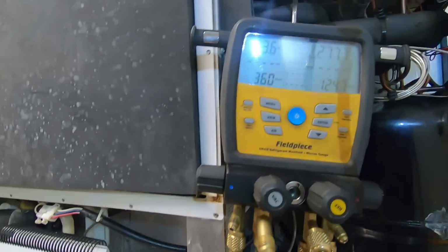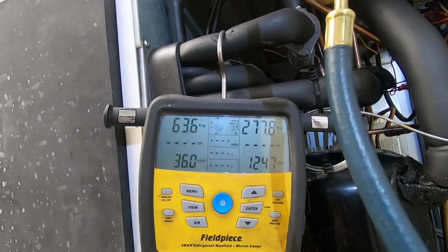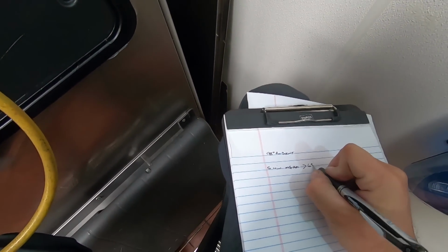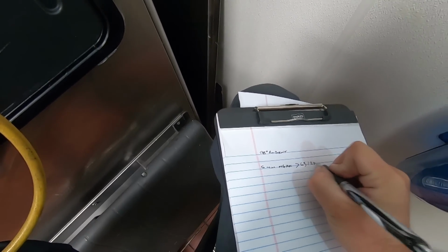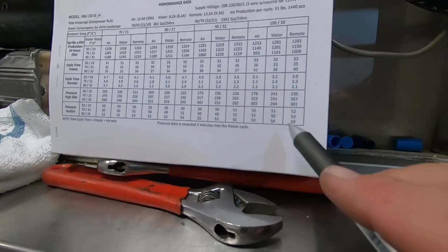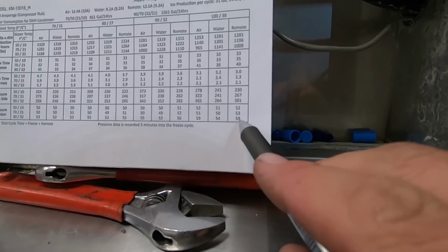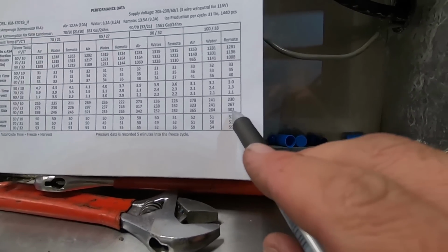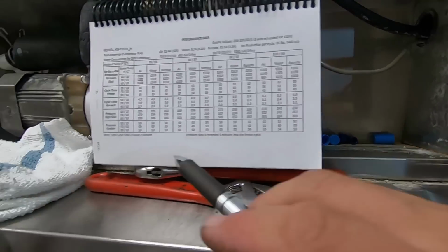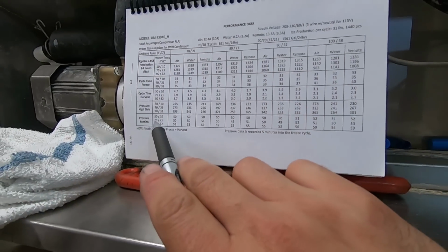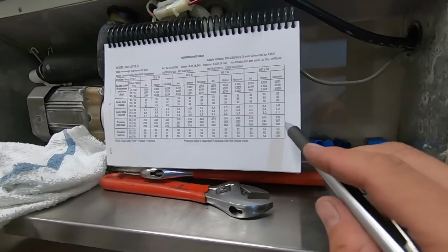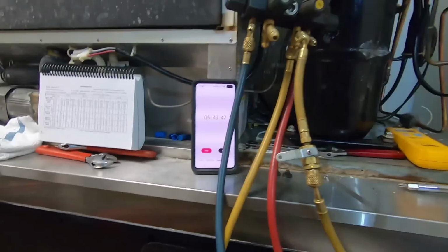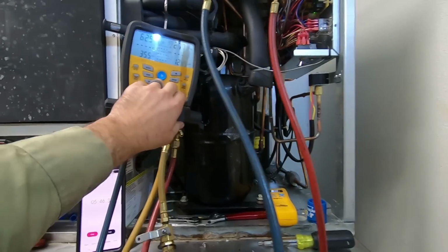All right, so we just hit the 5-minute mark and we're at about 63 and 277. So we're a little bit high on the suction pressure, but much better compared to what it was before. We're going to let it run a couple cycles. The book says for 100 degrees, at the most 59 and 301, and at the lowest 230 and 52, and that's dependent on your water temperature. So I would imagine our water temperature is somewhere in the 70-degree range. So we're not bad at all. I'm just going to watch it make a couple batches of ice and then start cleaning up my messes.